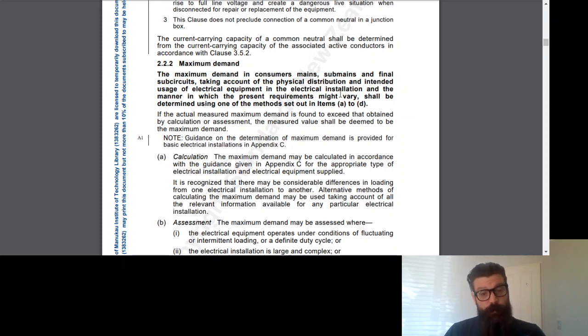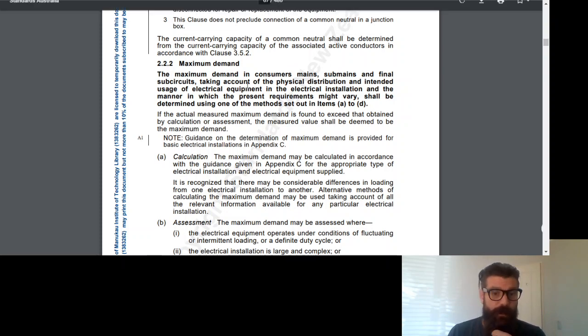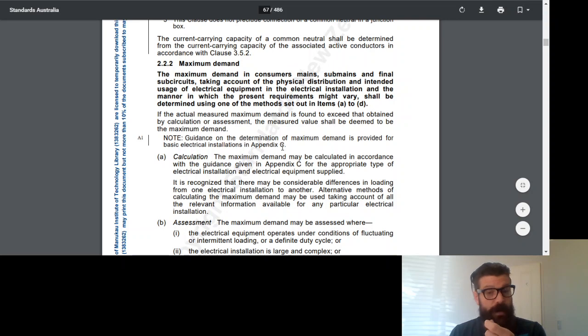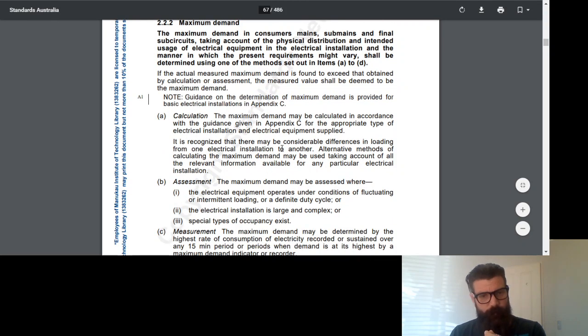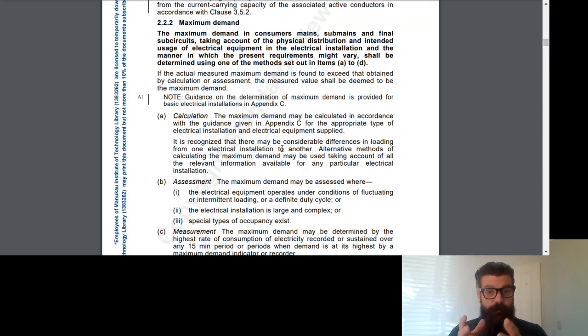Because when we use that to decide how big our cables need to be, how big our main switches need to be, all of that kind of stuff, because all of those things are defined by how much current I'm going to carry or how much power we're going to be using. So the more power I use, the bigger the cables will need to be, so on and so forth. Hopefully that makes sense. So this clause here gives us a way of calculating what the maximum demand will be. Because as you can imagine, if I just said to you, here's an installation, tell me what the maximum demand is, well, I don't know what's in there. How is it going to be used? This section tells us how we can calculate that.